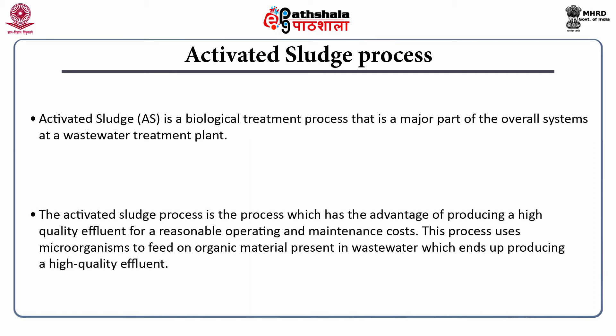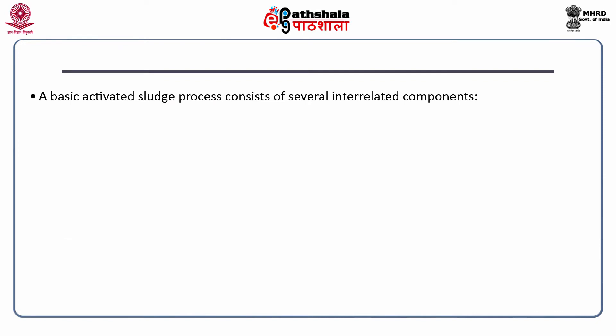Activated sludge process is a biological treatment process that is a major part of the overall system at a wastewater treatment plant. It has the advantage of producing a high-quality effluent for a reasonable operating and maintenance cost. A basic activated sludge process consists of several interrelated components. The first component is an aeration tank where the biological reactions actually occur. These aeration tanks may be of different shape — square type, circular type, etc.